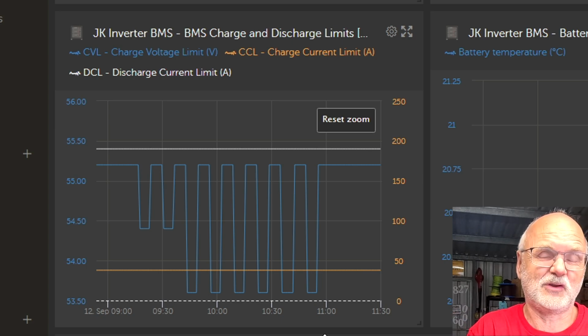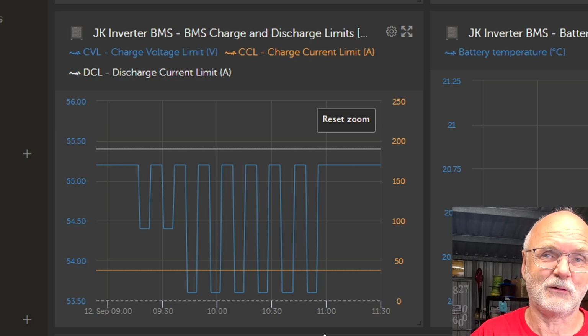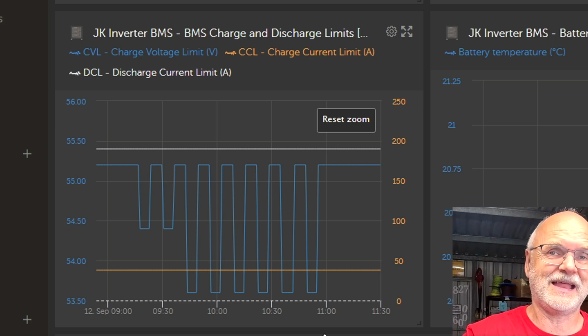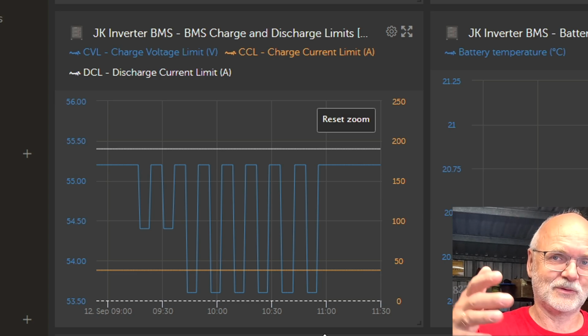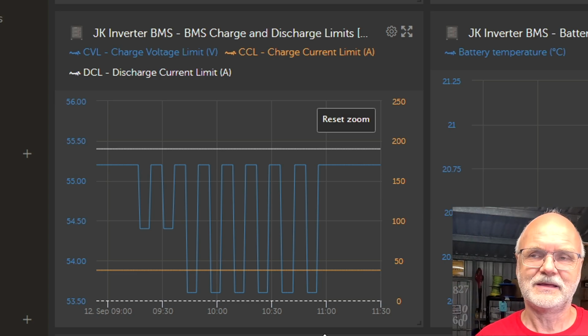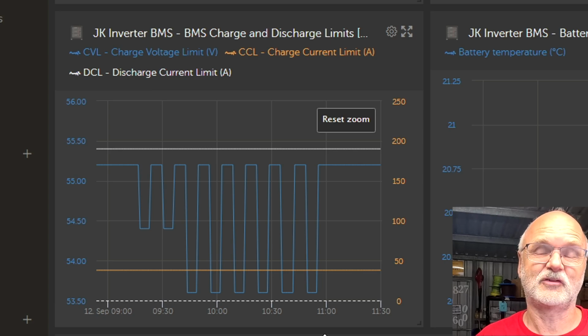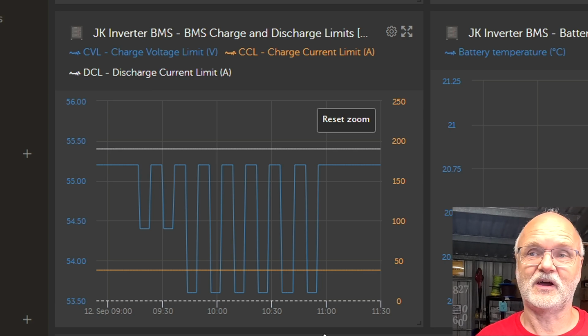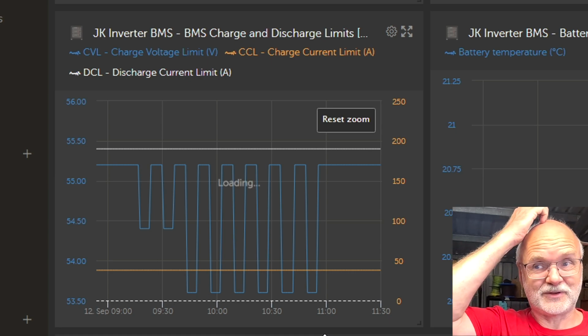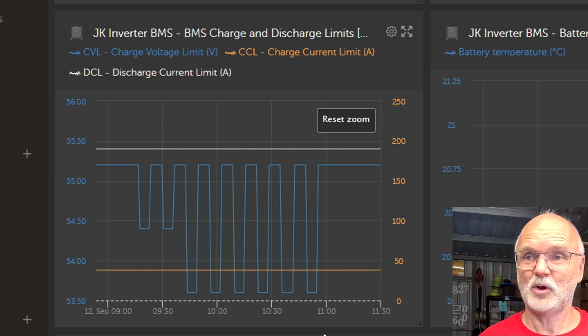Usually you would set the float timer to 5, 6, 7, 8 hours or something, so it resets in the night, and the next morning it starts with a fresh cycle and rebulks, charging your battery up again to absorption voltage 55.2 volts, and then the whole cycle starts again. This was after the update this morning, so it's already perfectly working.